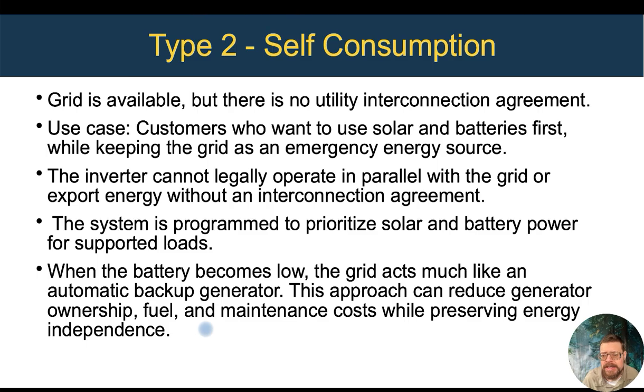And we program it so we obviously use our own battery power and solar as much as we can, but if we have to, we'll switch back to using the grid. It often makes more sense, if you've got the grid available, to use it as the backup rather than a generator, because even if you're paying $50 a month just to have the grid there and not use it, that's still usually cheaper than having your own generator and keeping up maintenance and fuel and all those costs that are associated with having your own generator on site. So that's really the background behind a type 2 system. It's really kind of like an off-grid system, but we do have the grid as backup instead of a generator.